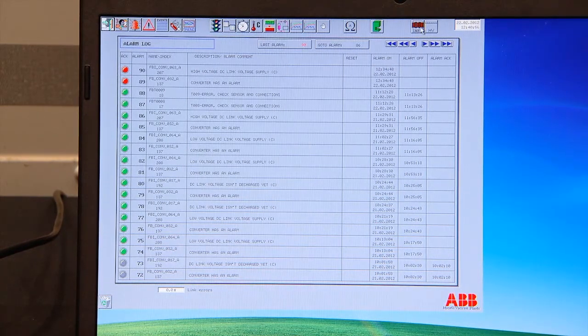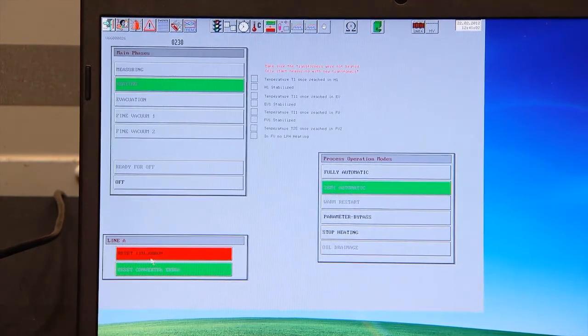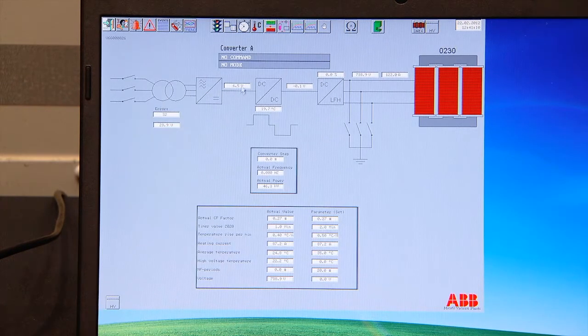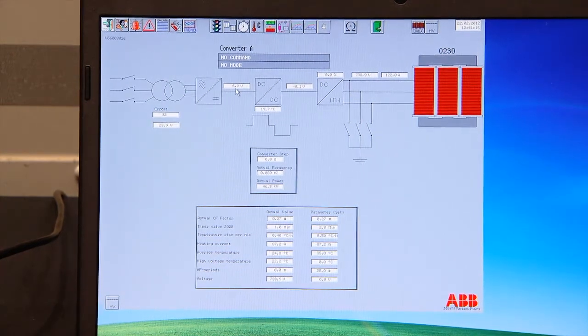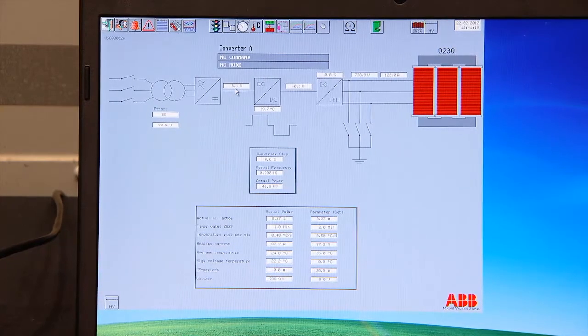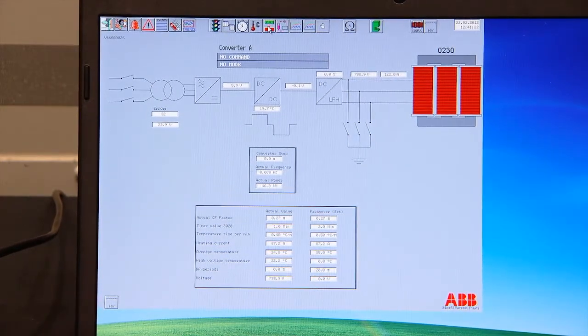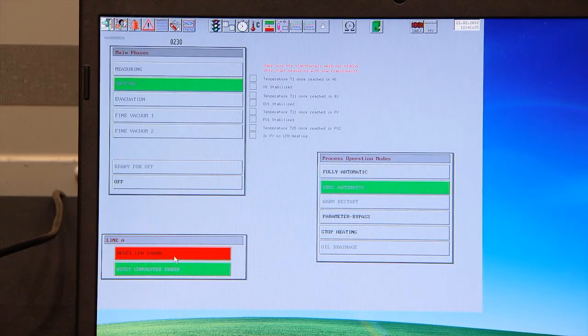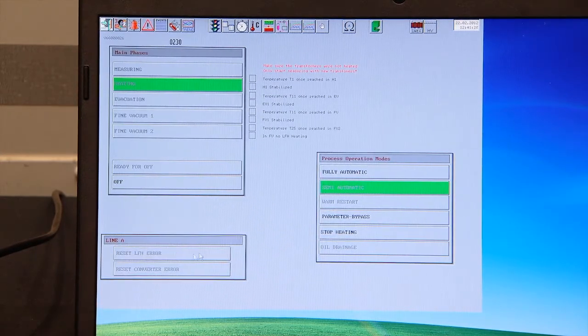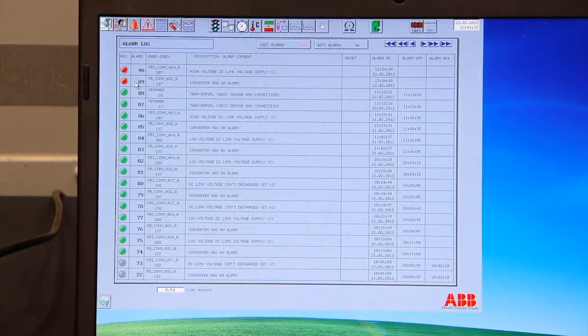When you have an alarm like this, you have to reset it. On the same page as start and stop, you will have a button called reset LFH error. That's highlighted red. Before you press that one, you should check the DC link voltage. This one here should be below 42 volt. If it's not, it will not be able to reset, or it will reset, but you will get the alarm back. So you can reset by clicking. The alarm here is that the voltage was still higher than 40. It would not allow you to reset it if you have more than 42 volt.